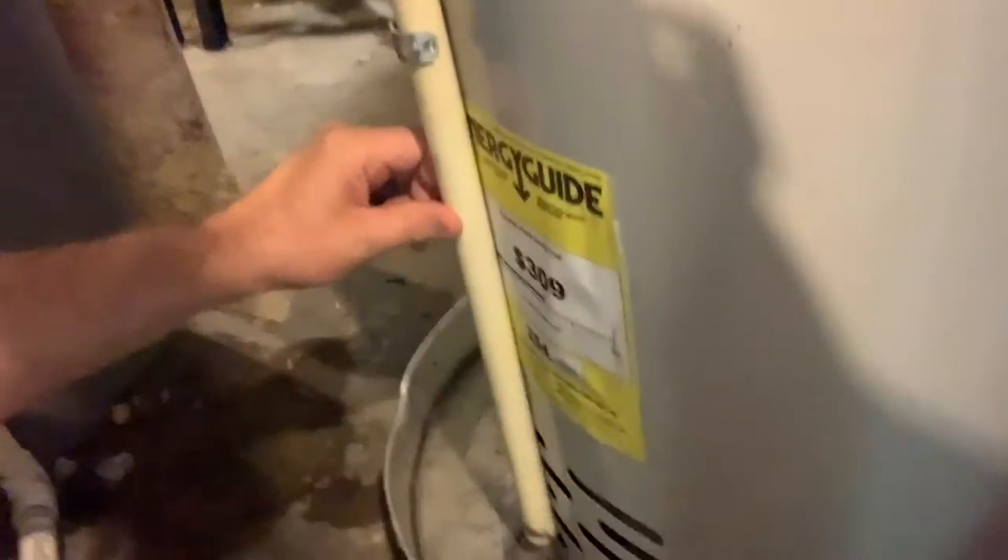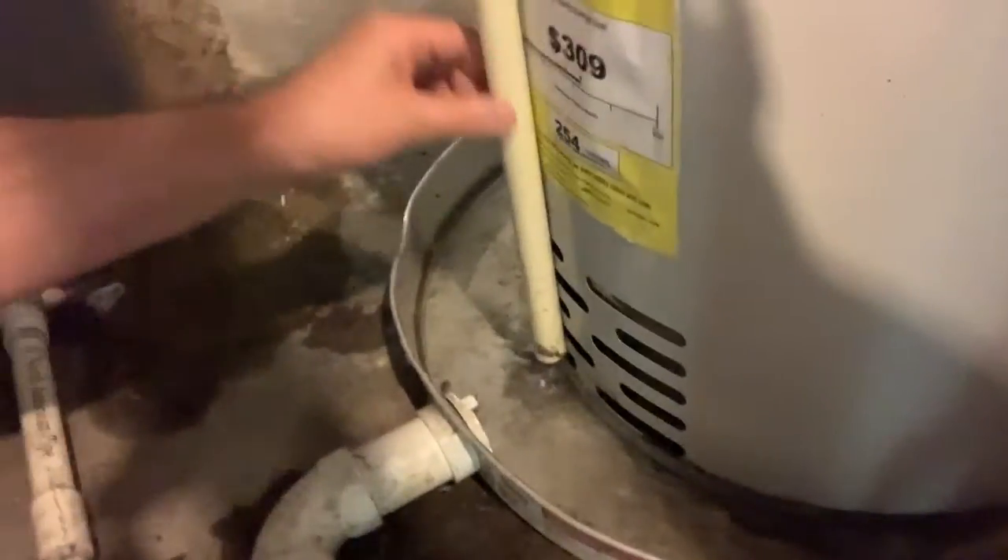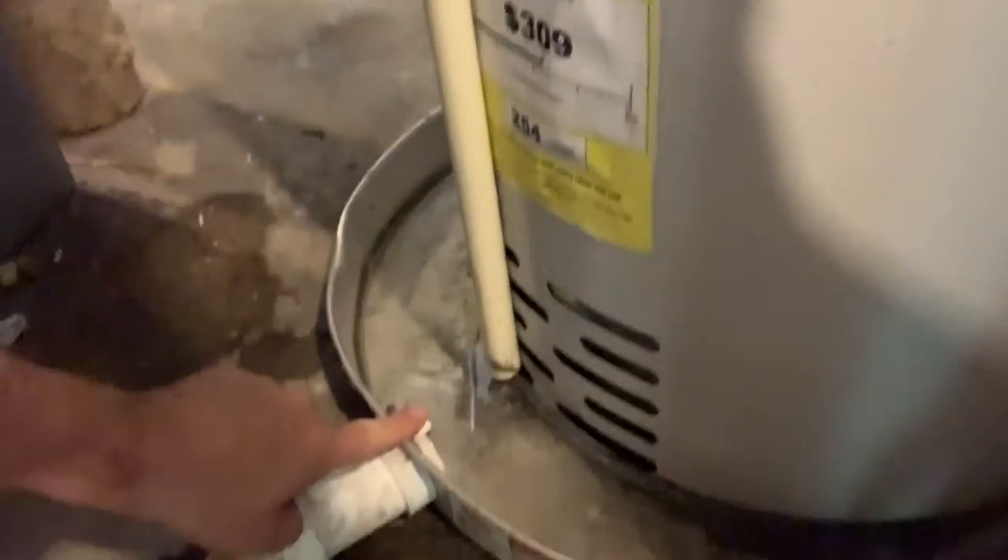All right, everybody, I'm back. Why do you even think you might need your T&P relief valve replaced? Well, you might come along and notice that this part on your tank is actually leaking. This is the drip tube that comes off of the T&P valve. And if you see that leaking into the drip pan, you might want to get a plumber involved to check it out, because that device is just so important.